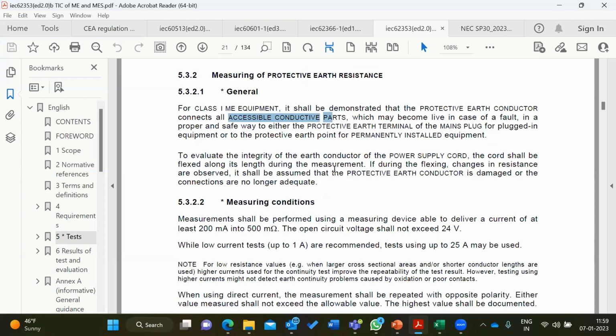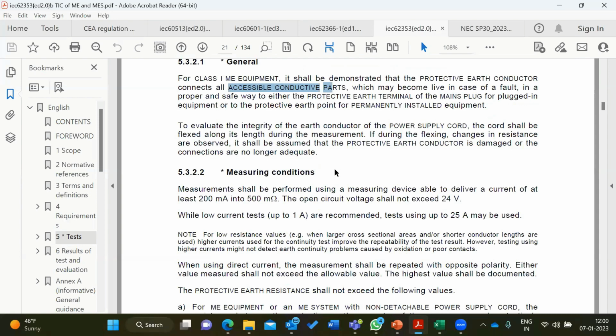And after repair, before you connect it to the service again, you are supposed to take a measurement of the continuity resistance. Continuity resistance means you should find out the connection is proper and it is strong. Measurement shall be performed using a measuring device able to deliver a current of at least 200 milliampere to 500 milliohm. The open circuit voltage shall be 24 volt. While low current tests up to 1 ampere are recommended, tests using up to 25 amps may be used.